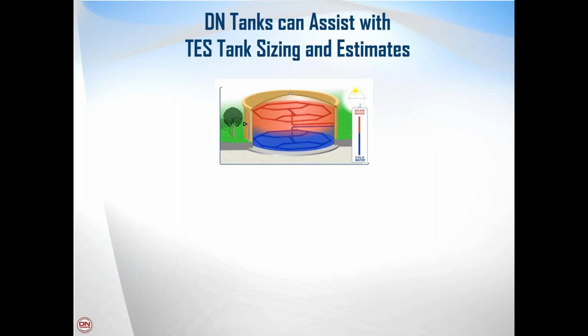The only other advantage, Lonnie, that you asked about, other than just space, would be that in very small sizes, they will be a lower cost option than chilled water tanks. But the opposite is true when the systems are very large. When it's a large campus type system, it's usually less expensive for a chilled water system than an ice system. The tanks become very much lower in cost as they get bigger.